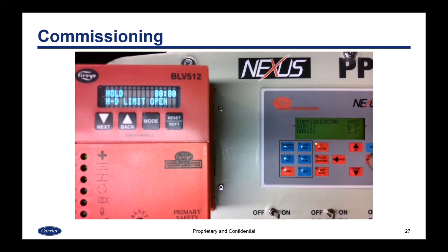So now I would make any adjustments, except I'll leave it the way it is, and I'll hit next, and then it'll actually proceed with ignition. So now we're in PTFI. And it'll go through PTFI and it'll go to MTFI just like before. And we're at the ignition position, 0.2. So now it's in auto, and now it wants us to verify 0.2 again, which is a little different than an NXF, but that's because with revert to pilot, like I said, you could light off at that same position. But then it went to 0.3, so I set and applied 0.3.